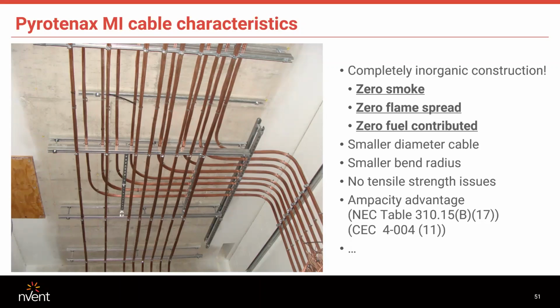And also, per table NEC 310.15(B), you can use a free air rating with our single conductor cables. So that does give it a big ampacity advantage. For example, our 500 kcmil cable has an ampacity rating of 620 amps with a free air rating. And all the other single conductor cables have the free air rating as well. Our 250 kcmil is rated at 405 amps. So it does give you a bit of an advantage there.